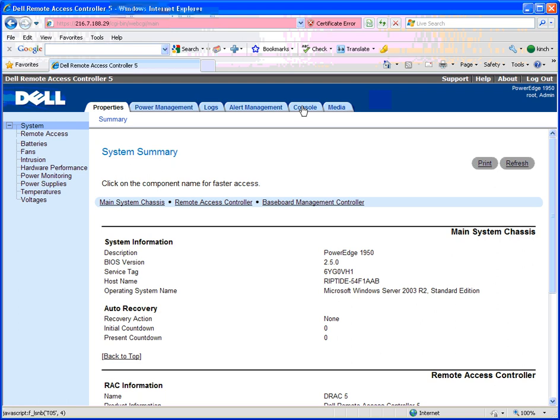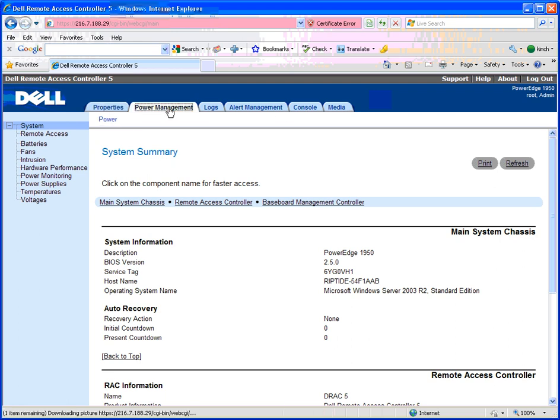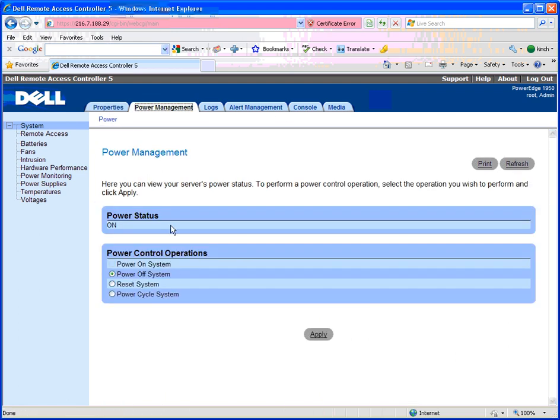So, at first, we'd recommend that you console into the server to see if it's in a good state. If, at that point, it's locked up and you can't do anything, you'd come over to Power Management, select it, and you can see the current status.